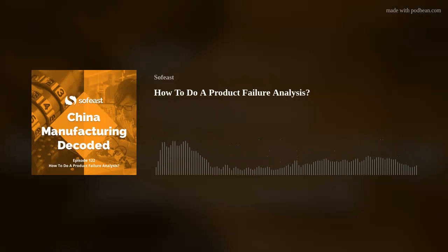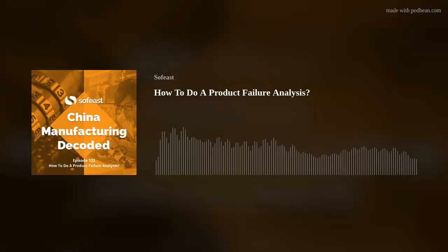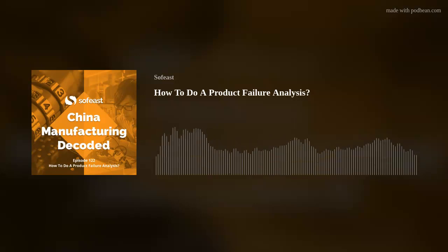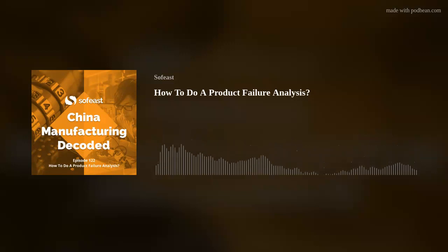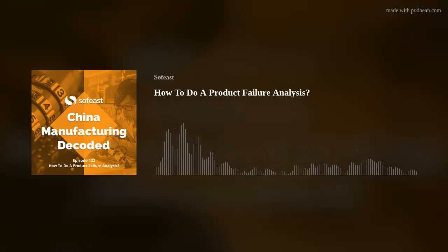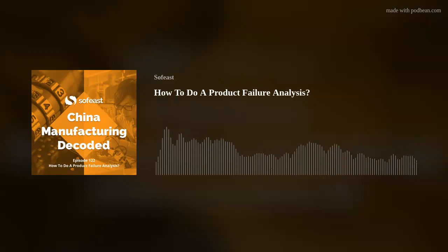A good example of this is probably last week's podcast episode with Andrew, where we talked about the big medical device recall by Philips. You can bet your bottom dollar that Philips went back through and did a failure analysis like this in order to make the decision to do a huge product recall and to understand why. It's interesting that it's a must by law under the EU medical device regulations or US FDA 21 CFR code, depending on the country where they sell.